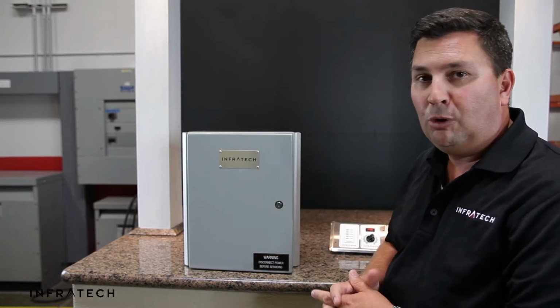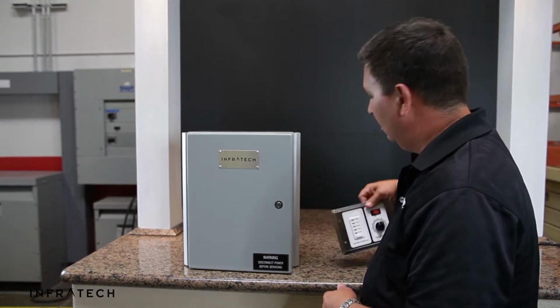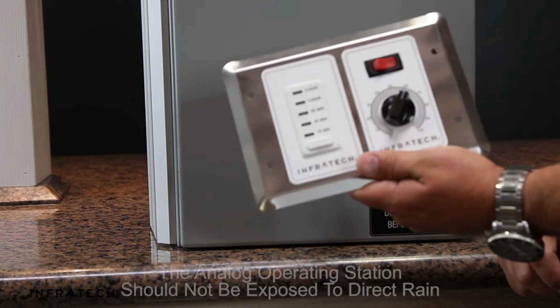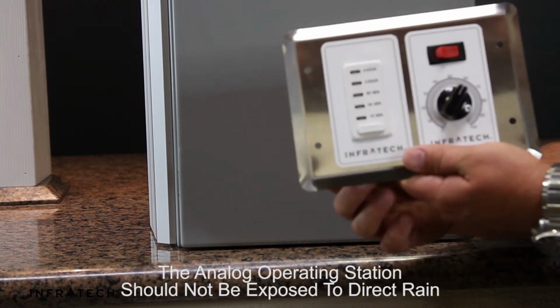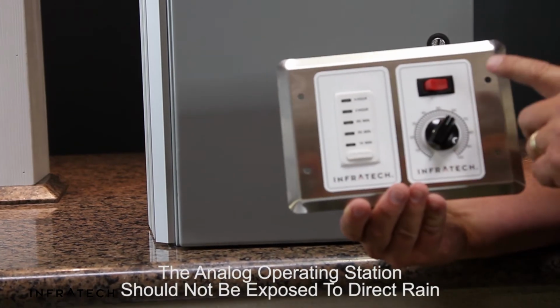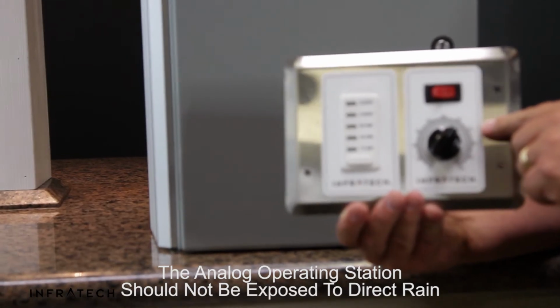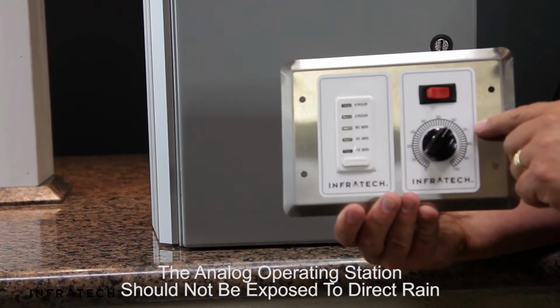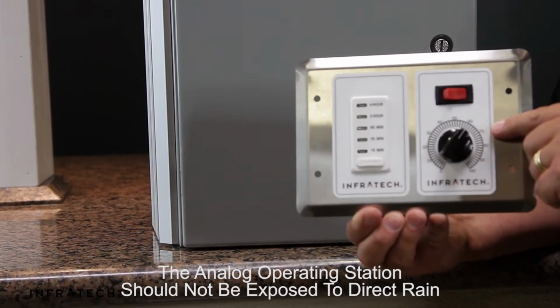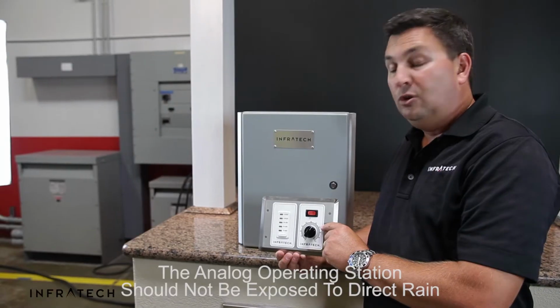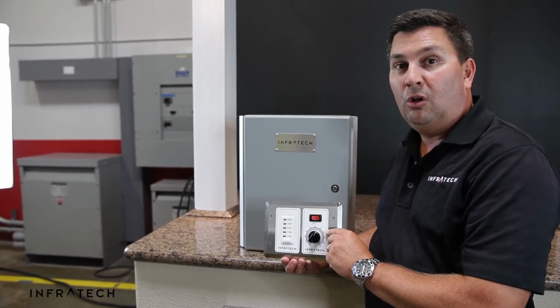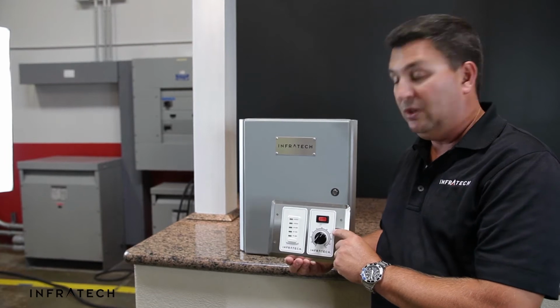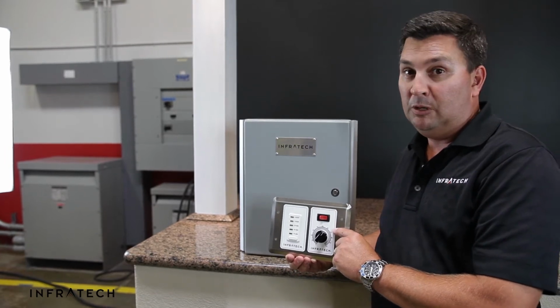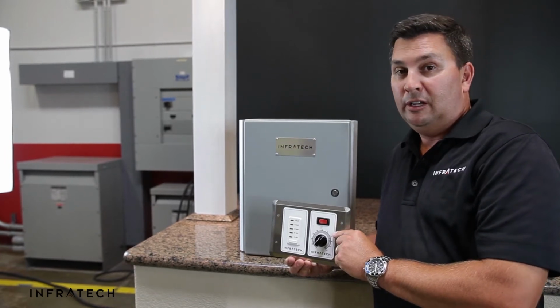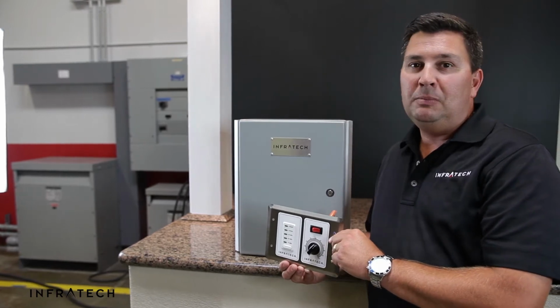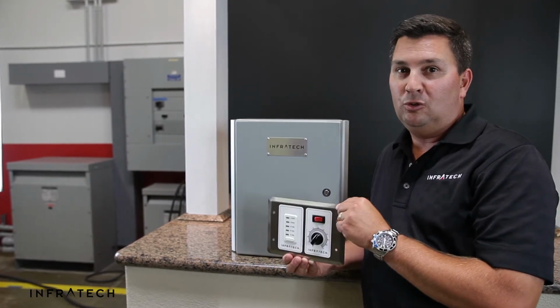Once you've selected an appropriate location for the main relay control, you'll need to select a location for the analog operator station. This can be out on the patio near the heaters, but the analog controls are only NEMA 12 rated. That means they're suitable for dust and mist, but not direct rain. You'll need to install the analog control under a solid roof or an area where it will not be exposed to direct rain. That could be behind a door on a barbecue island, it could be inside, it could be anywhere near the patio that is well protected.